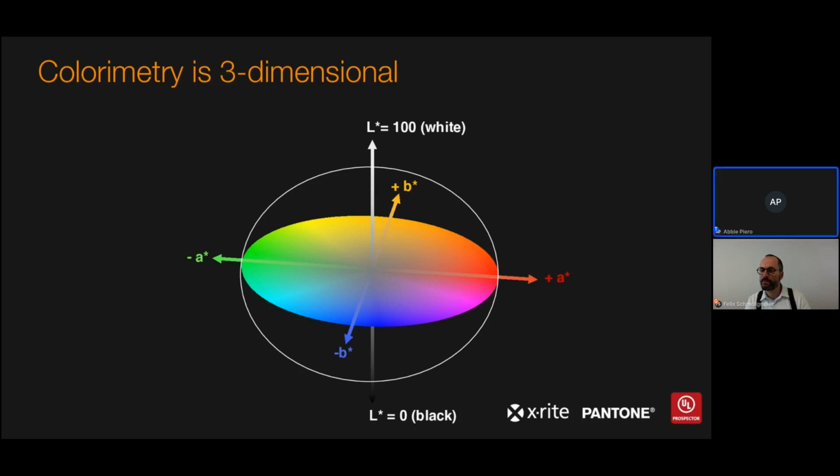Okay. Our next question: how accurate are handheld and tabletop machines? And with that, what temperature is best to measure color during mass production using a tabletop machine? Always, the standard temperature range of 72 Fahrenheit or 22 degrees Celsius and a mid-range relative humidity is the best condition. I'm trying to answer a second question here, which was: when you have to profile the spectro, do you have to set it up at the same temperature as the reference instrument? Ideally, yes, but Net Profiler does have a temperature compensation.